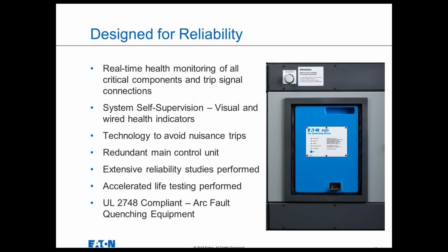So the system's been designed to be super reliable. As I mentioned, it's got real-time health monitoring of all critical components and trip signal connections. So it provides dry contact health outputs, Modbus. There's a local indication on the equipment, just a white light that's illuminated that says the system's healthy. As I mentioned, there's technology to eliminate the risk of nuisance trips, because the last thing you want to do is take your board offline if it wasn't a true arcing fault, if it's just an accidental event. That's the last thing you want to do.